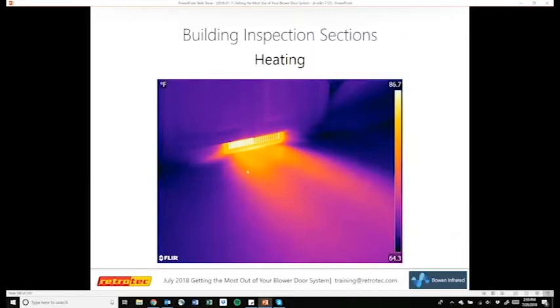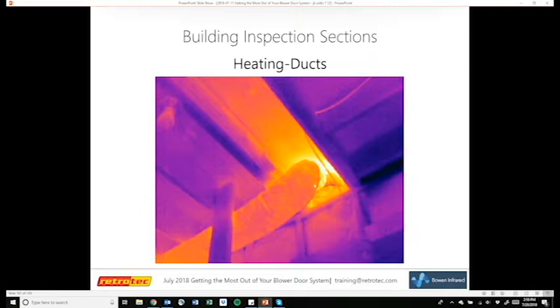Sam talked about doing some HVAC work with blower doors and pressure pans. I've had the opportunity to do the same with thermal camera, where I can look at diffusers and really decide if this pattern of air coming out is correct for the diffuser. And I've seen patterns of air that come out because of crushed duct, compressed, flexible duct, things like that. And here we've looked at a duct system that's making a transition from a joist enclosed type of duct to a flexible duct. And they put a tie wrap on this flexible duct piece to hold it to this flange. And the last time I checked, tie wraps are not air sealing any kind of gap here. So it's going to show up pretty readily.